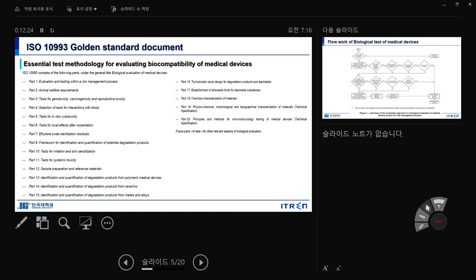Part 1: evaluation and testing within a risk management process — a general overview. Part 2: animal welfare requirements — how you deal with animals, including minimal requirements like feeding. Part 3: tests for genotoxicity, carcinogenicity, and reproductive toxicity. If a material is inside your body when you have a baby, toxic substances could be delivered to the baby through the blood vessel barrier. Part 4: selection of tests for interaction with blood — how you evaluate blood interaction using your material.